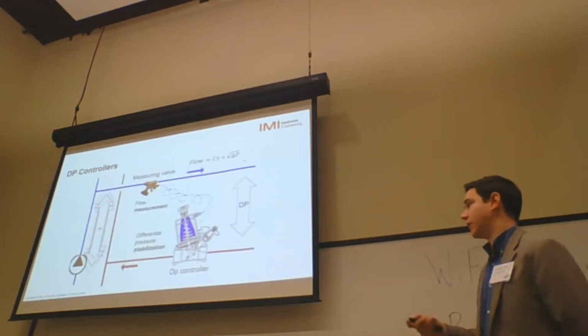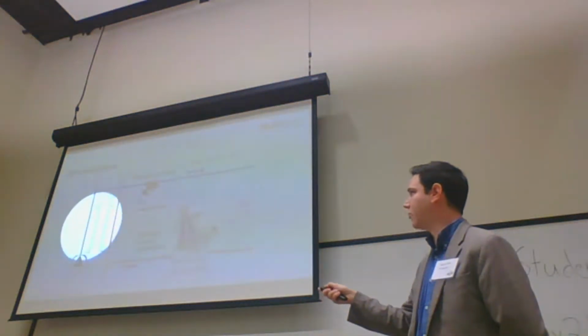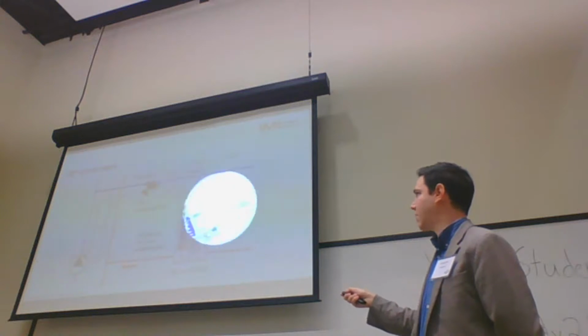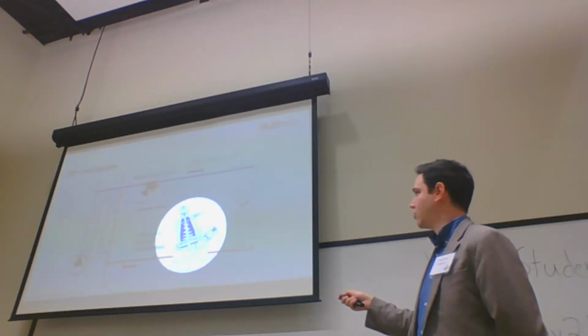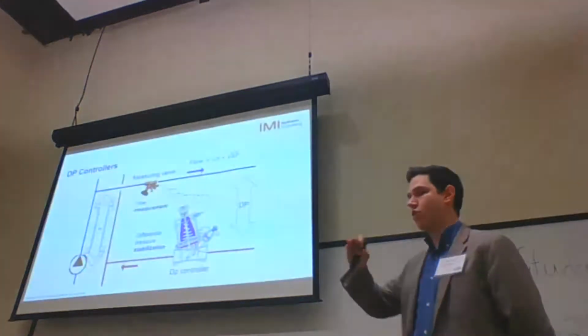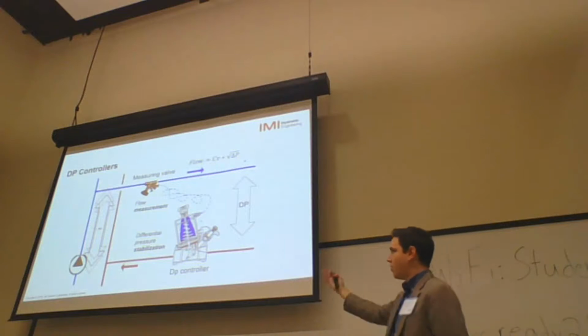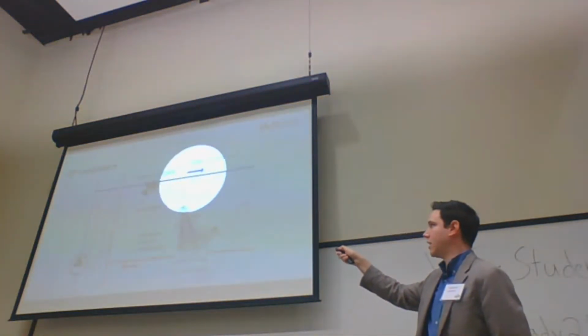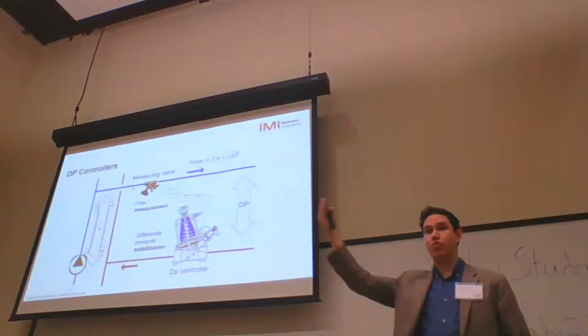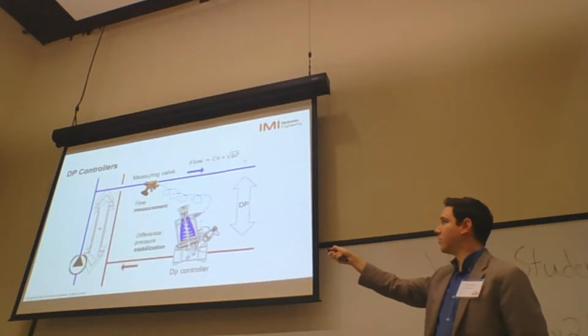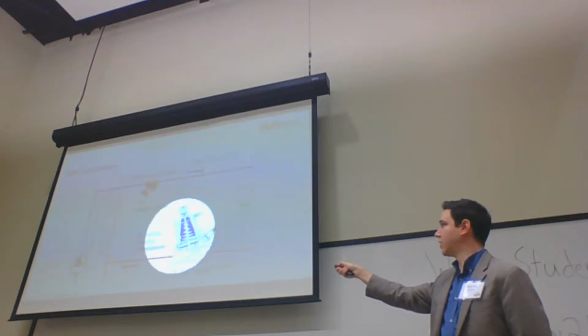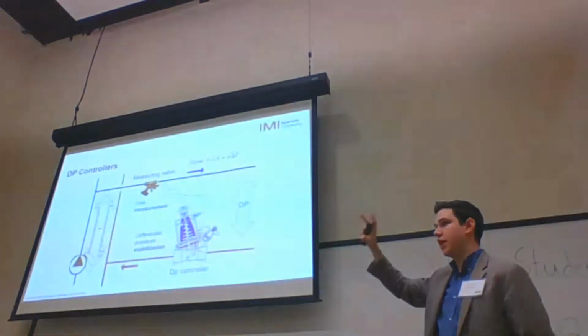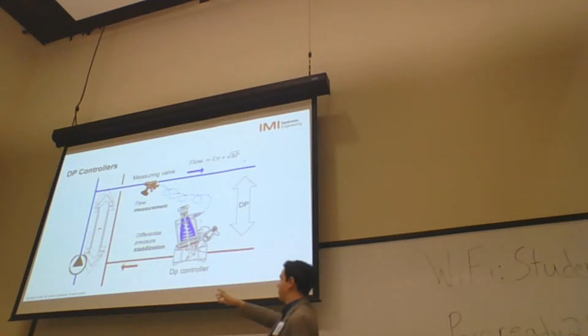The mechanics of the valve. Here in this example, I have my pump. The blue line is the supply. Here's a manual balancing valve, a capillary tube connecting the two valves, and this differential pressure controller, always on the return. There is a membrane right there, dividing the water from supply and the water from the return. The way the valve works is if the water on the supply increases the pressure, and that could be caused by other branches shutting off or whatever you're doing in the rest of the system, if the supply of this branch starts to increase the pressure, it will increase the pressure on this capillary tube, it will increase the pressure on the blue part of the DP controller and push the membrane down to also increase the pressure on the return to keep the same differential for the branch.